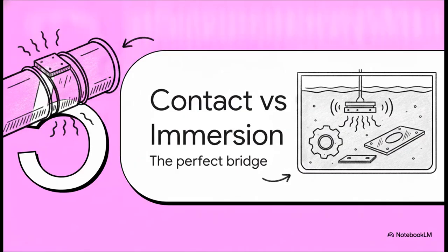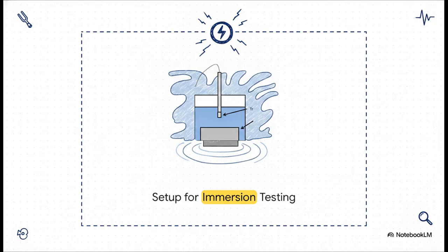Section 5. Contact versus immersion testing. Let's look at the different environments where we create that perfect bridge. Now let's look at an immersion testing setup, like the diagram we have right here. Let's visually follow the signal from top to bottom. Way up at the top, you can see the electrical cable leading down into the transducer probe itself. But notice something super important.